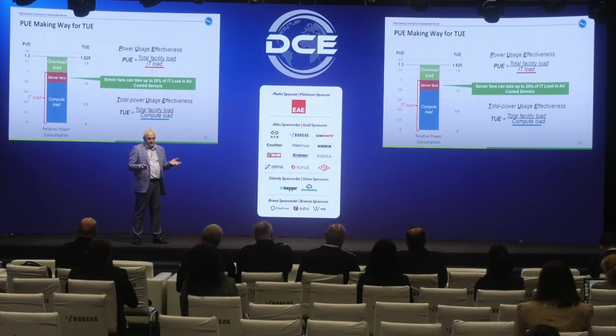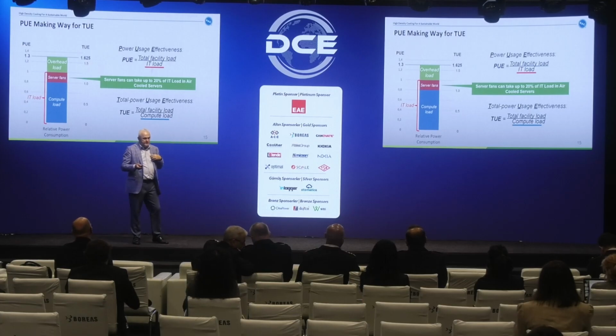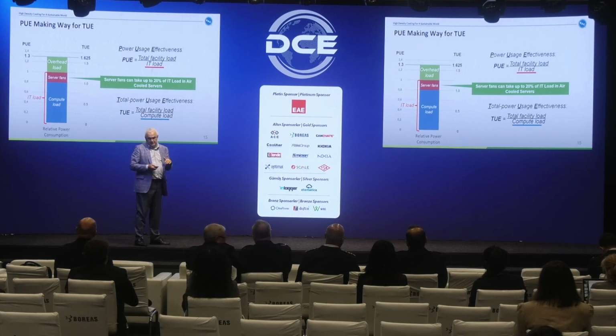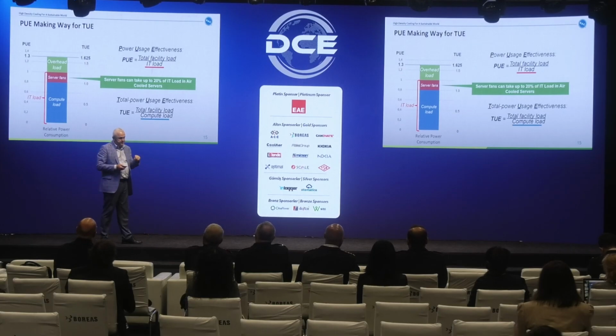It's not IT load. With immersion cooling, you're able to use that 20% for your core business, which is data storage and computing. So the new KPI in the industry is called total usage effectiveness, which gives a more accurate picture of how efficient your data center is—total facility load divided by compute load, not IT load, so now you know exactly how efficient your data center is.